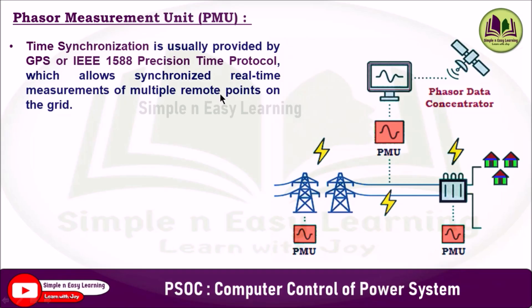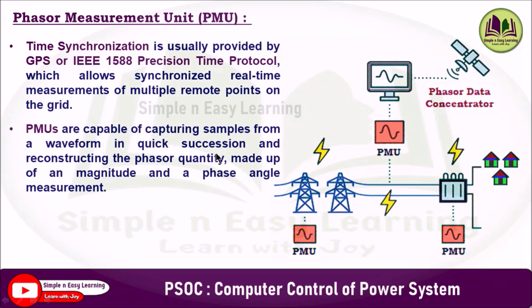IEEE 1588 Precision Time Protocol allows synchronized real-time measurement of multiple remote points on the grid. It is a standard for synchronizing clocks on a network with sub-microsecond accuracy, and it distributes time and frequency information over a packet-switched Ethernet network.